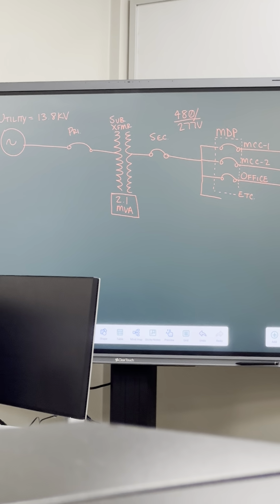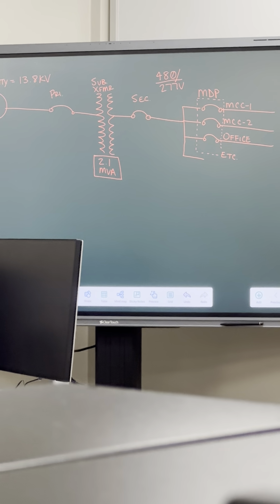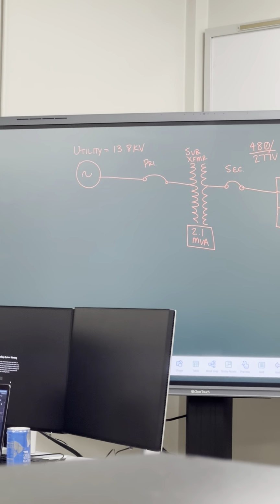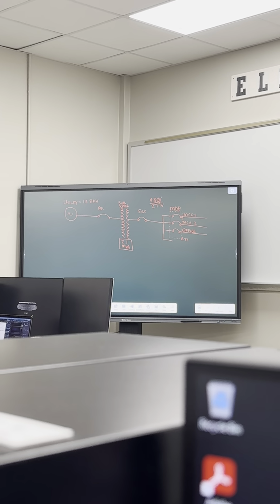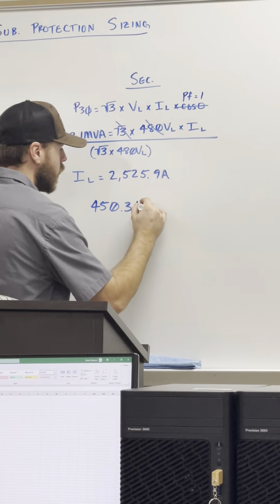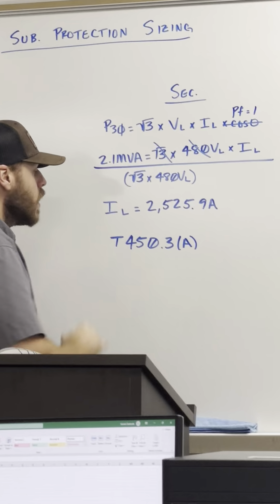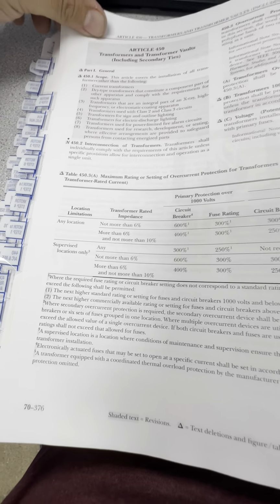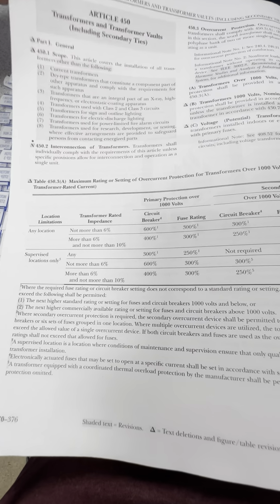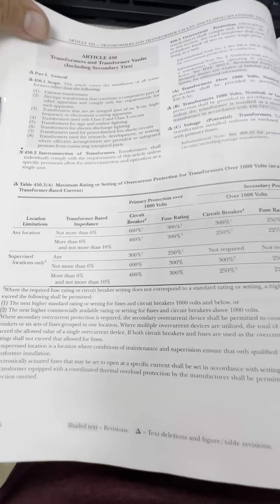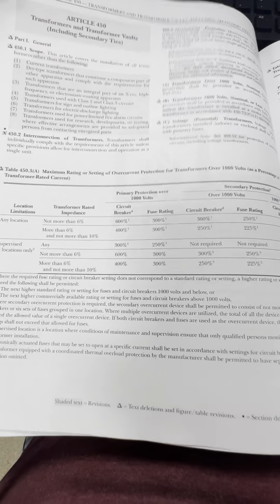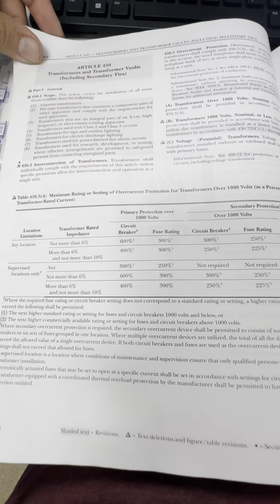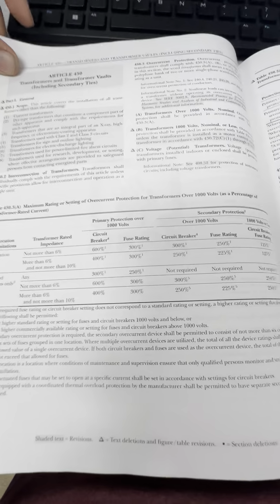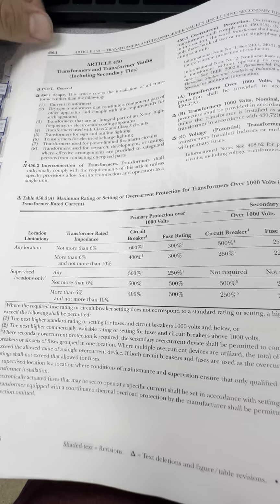So looking there, option A, it says transformers over 1,000 volts nominal. Does that fit our description of the substation transformer? Yes. Yes, absolutely. So this week, we're gonna look at option A there. So that's gonna direct us to table 450.3(A), which is really nice, because that's just right there below it. It's a little bit larger table than last week. But in the title of the table, at the end, in parentheses, it's still important. It says, as a percentage of transformer rated current. That's why we solved for this little over 2,500 amps here. That's our transformer rated current.